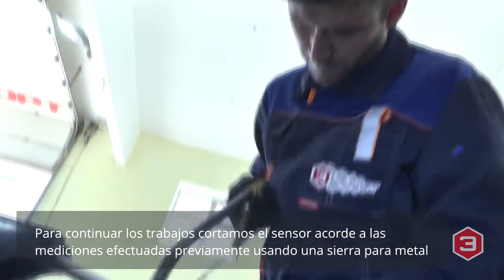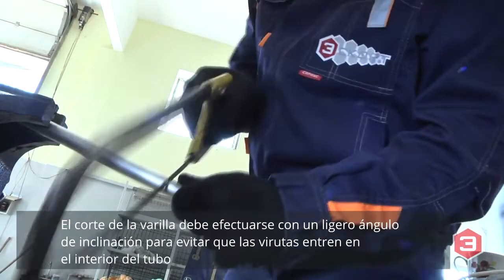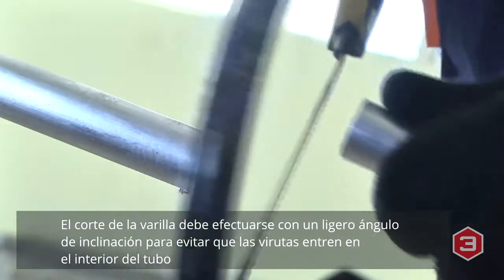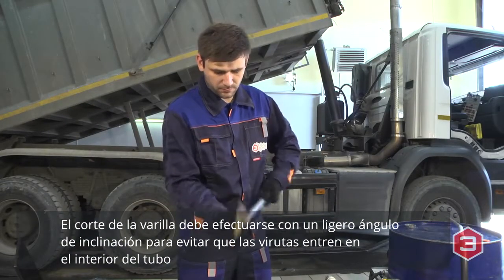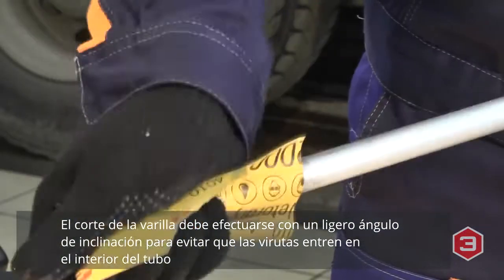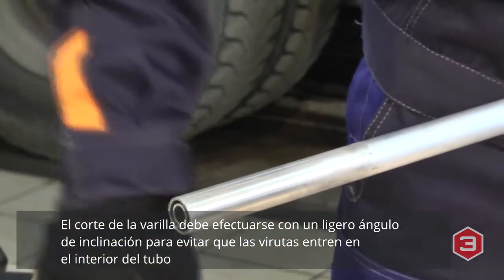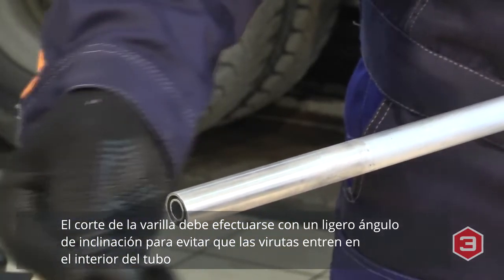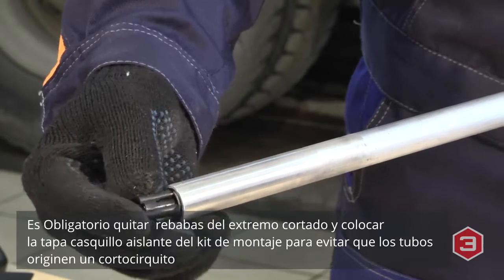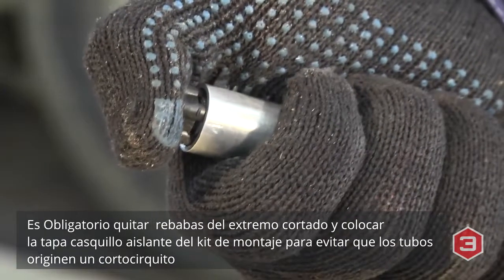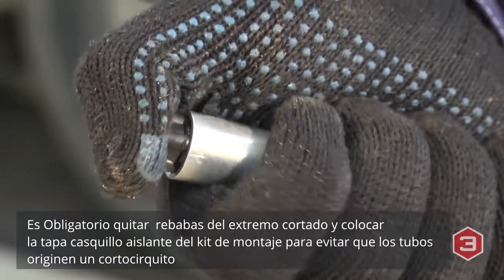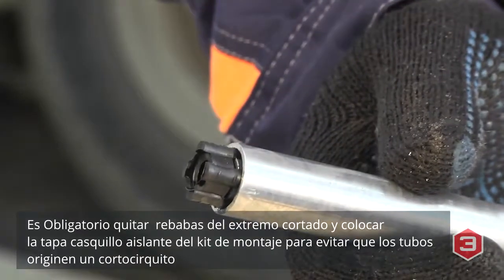Adjust the sensor length using a hacksaw. Cut the excess parts of the measuring tube at a slight angle in order to avoid metal chips getting inside the tube. Deburr the edges and then insert the insulating cap from the installation kit, so that the internal tube doesn't touch the external one.